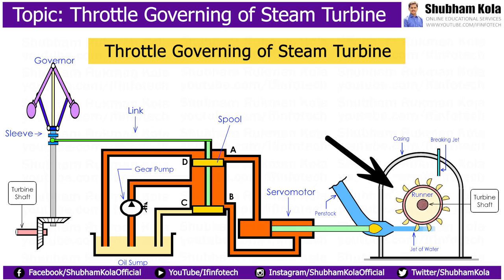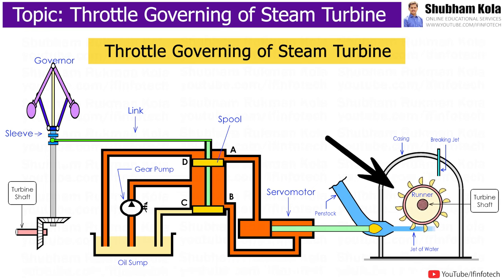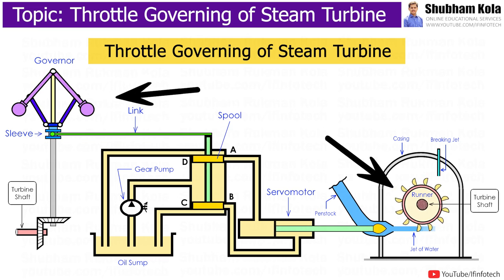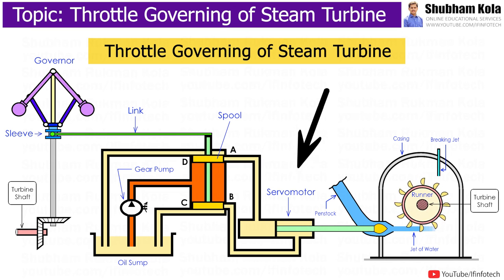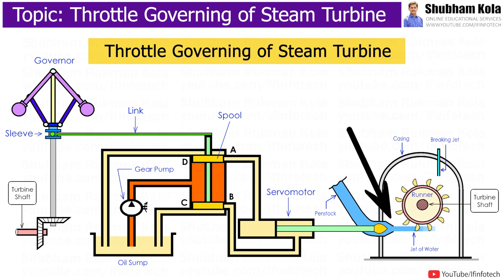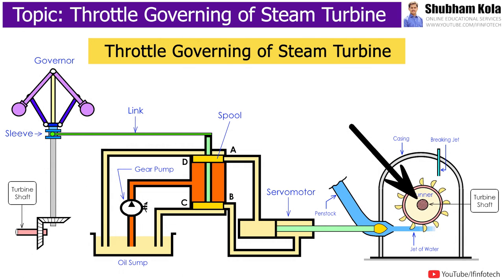Ultimately, the system will reach equilibrium again. When the power developed by the turbine equals the load on the turbine, the oil ports are covered and the servo motor is locked. In this way, with the help of throttle governing, we can control the power output of the turbine according to the load on the alternator, by keeping the rotational speed of the turbine constant.